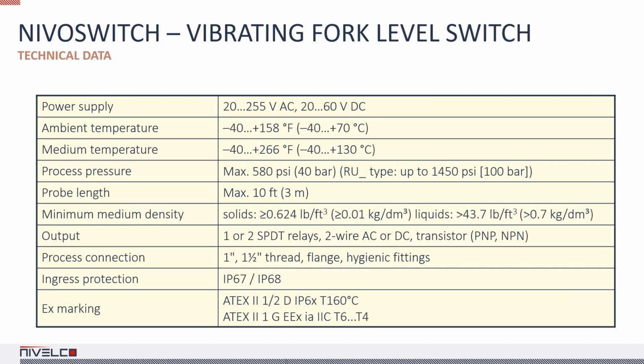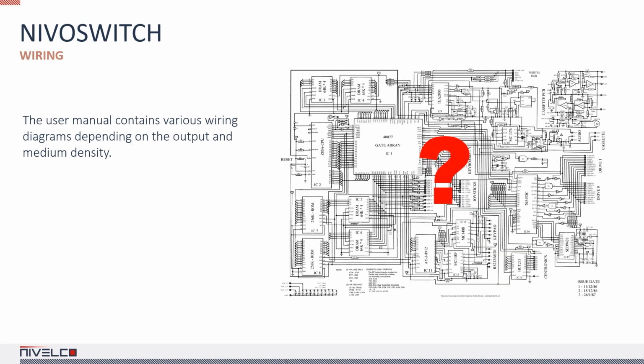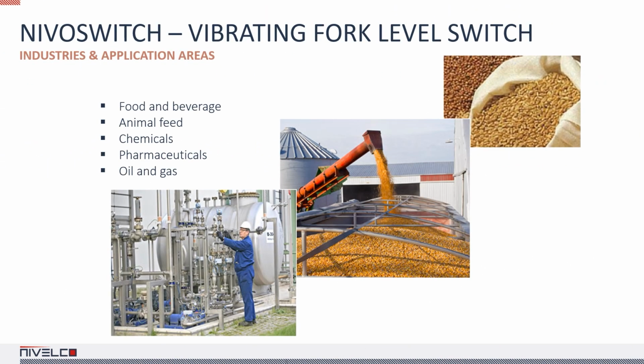NivoSwitch vibrating forks combined with Unicon PPK switching amplifiers can be used with high current loads. The Unicon PPK312-8EX intrinsically safe switch unit is designed for EX vibrating forks. The user manual contains various wiring diagrams for different outputs and medium densities. Units with parallel vibrating prongs are ideal for liquids, and units with diverging vibrating prongs are designed to measure solids. The plastic-coated version is recommended for aggressive mediums, and the highly polished version is for use with abrasive materials.